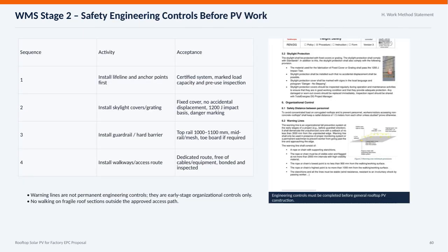Before starting any rooftop solar PV work, it's crucial that we first complete all necessary engineering controls to ensure safety. The key steps begin with installing lifelines and anchor points, which must be certified systems with clearly marked load capacities and be inspected before use. Next, skylight covers or gratings need to be securely fixed to prevent accidental displacement, built to withstand impacts of 1200 joules and marked with danger signs. Following that, guardrails or hard barriers must be installed, with specifications such as top rails between 1,000 and 1,100 millimeters high, along with mid-rails or mesh and toe boards if needed. Finally, designated walkways or access routes should be set up. These need to be free from cables or equipment, properly bonded, and inspected to guarantee safety.